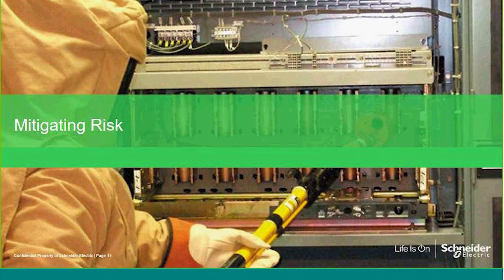And I've seen this myself in some substations where there is a sign to say none of this equipment should be operated with anybody inside this substation. A lot of the utility companies now, with their aging assets, don't operate equipment whilst they're stood in front of it. They use remote controls, they use lanyards. So understand the risk and remove the risk.